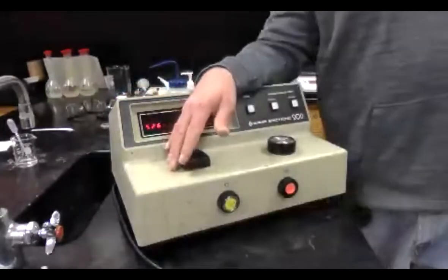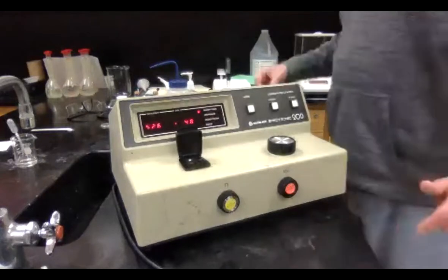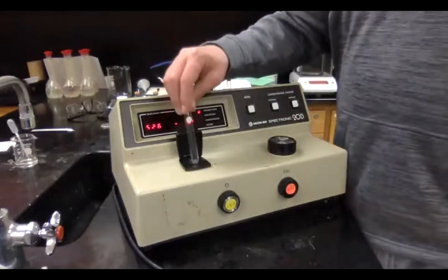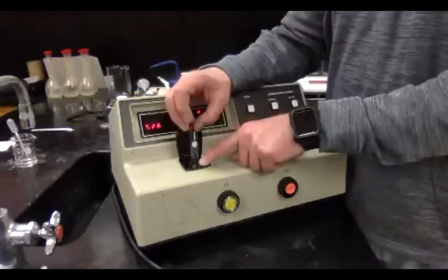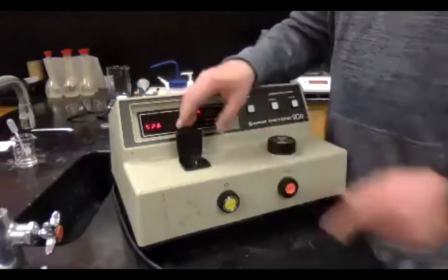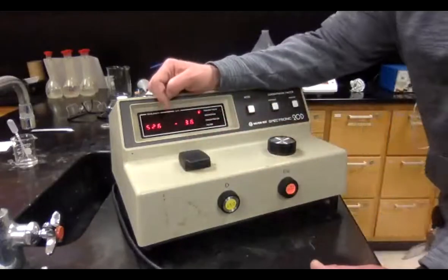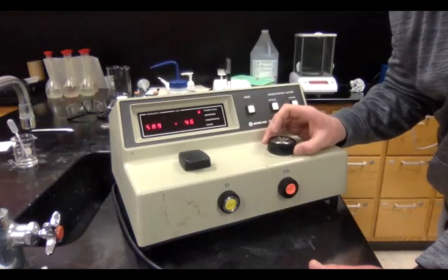So this is the machine. There is a light bulb right here. You can watch it up there too, up to you. This is where you put your little sample. Your sample goes in what we call a cuvette. It's like a test tube, but it has a specific line that you line up. There's a line on the machine as well. You push that down there, and then it reads it. Currently, I am at wavelength 526, right? I can use this knob to change my wavelength.